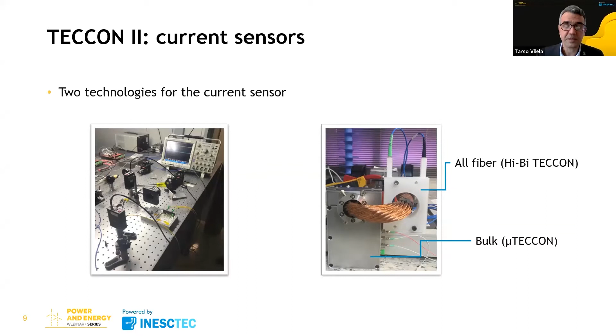Here we can see a test of the current measurement system. We have here the signal the photo detector has captured, and in the second graph we have the spectral behavior. Here we have 60 Hertz, which is the fundamental, of course. Both sensors are able to do this kind of detection. However, the high-bi, in theory, is able to detect faster phenomena such as surges, for example. But our other sensor, the micro TECCON, is also able to detect those surges, as we will see in the next slides.